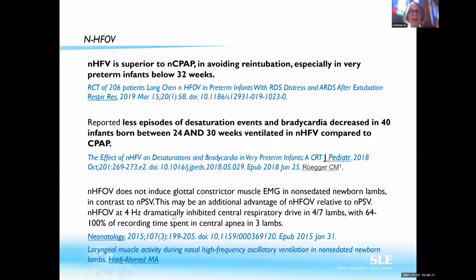An important factor is that whenever you push a breath, you might have the glottal constrictor muscle closing. Whenever the patient feels some air going to his lung, he might protect his airway by closing his glottal constrictor muscle. And sometimes, even if you push a breath, it will be closed, so you won't have any gas going to the patient. There's a risk whenever we do some IPPV or even synchronized IPPV, we might have the reflex of closing. So what we have found in the lab is that when you do NHFO, you don't have this kind of reflex. But what we found out is that when they were going quite low on the rate, the patients had a tendency of stopping breathing. So certainly don't use too low a frequency when we work in HF.